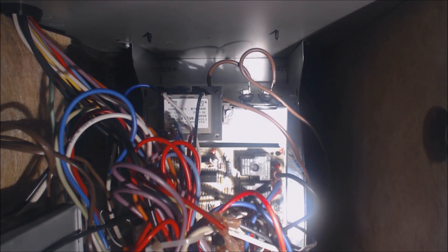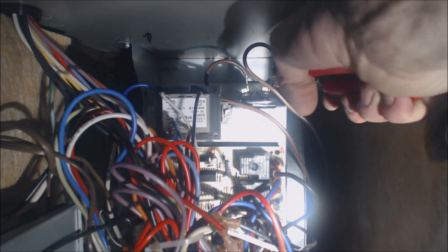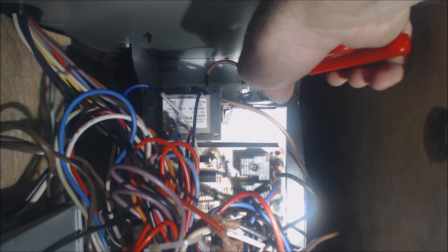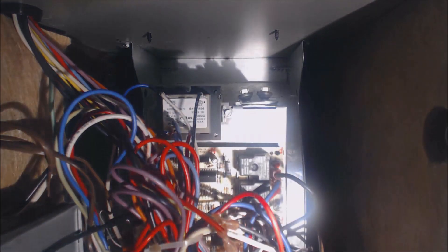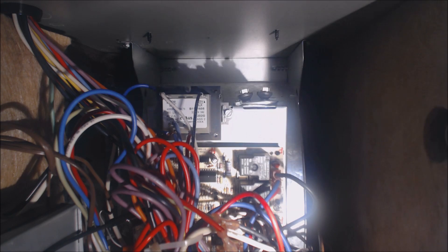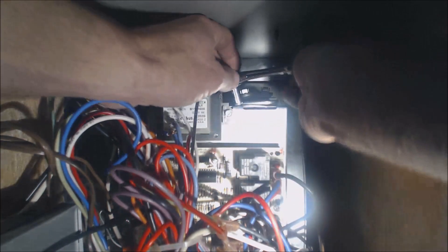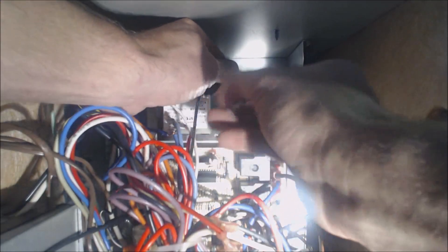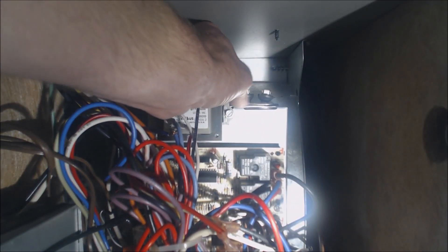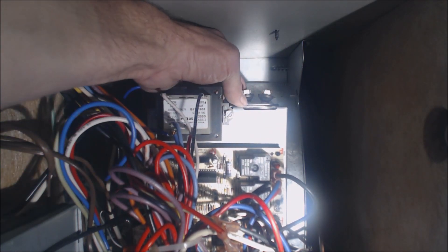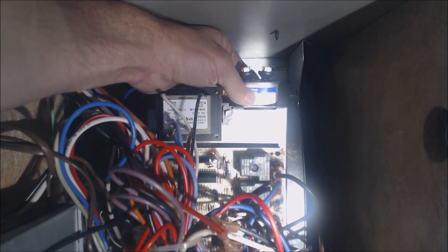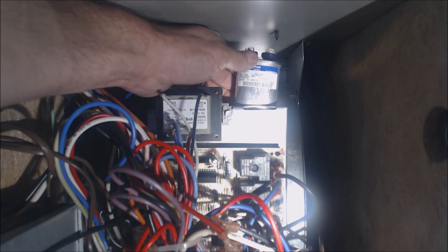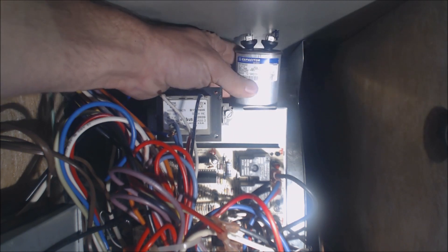Power is off, confirmed. We're going to pull the spade terminals off. You always want to use wire strippers and cutters. Then we've got to take that 5/16 screw out. After checking to make sure you have voltage going to the blower motor, the only other thing it usually is typically is the capacitor. Now the motor could be completely burnt apart as far as the windings go. Let's just test this before we can't completely get it all the way out here.